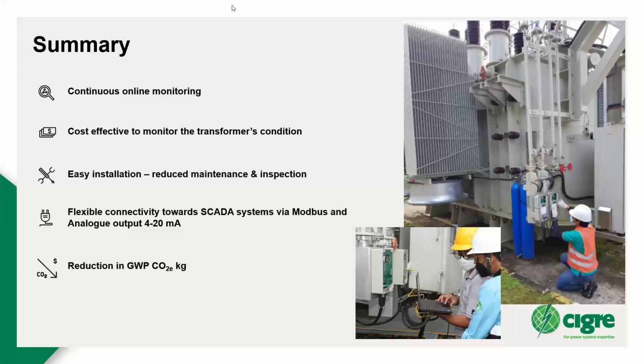The question is posted in the chat as well. What I've seen in the past is you do a bit of drying out, then turn the online dryer off, and the water content of the oil slowly increases again as it's transferring out of the paper. We did it over about a year, taking the dryer off, waiting for the water content to increase, putting it back on, letting it fall again, and doing that two or three times until it wasn't changing any further. I recall guides from about 10 years ago warning about paper cracking if dried out too much, because the paper shrinks, and if too degraded it might break or crack. I'm not up to date on that, so I don't know if anybody else has comments.